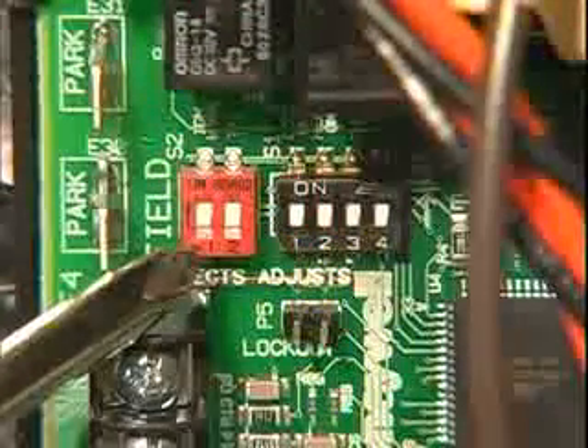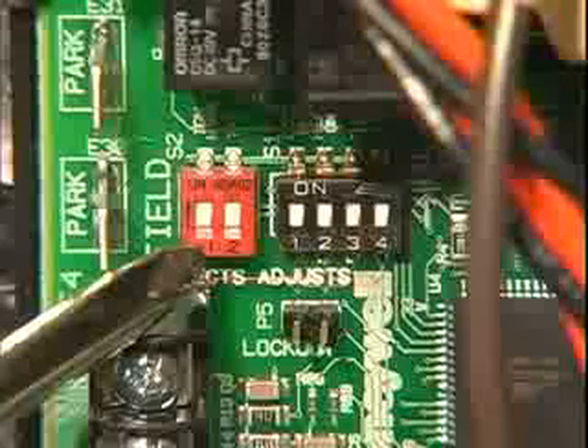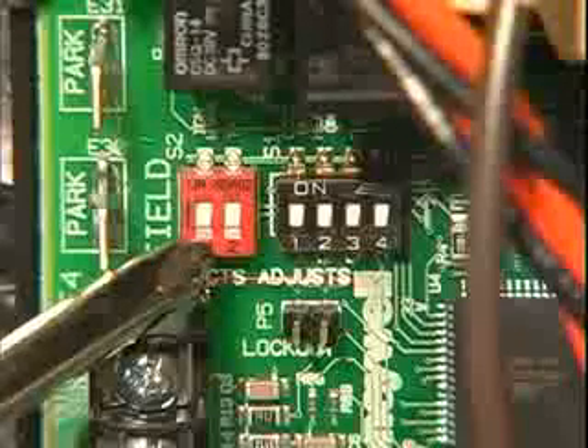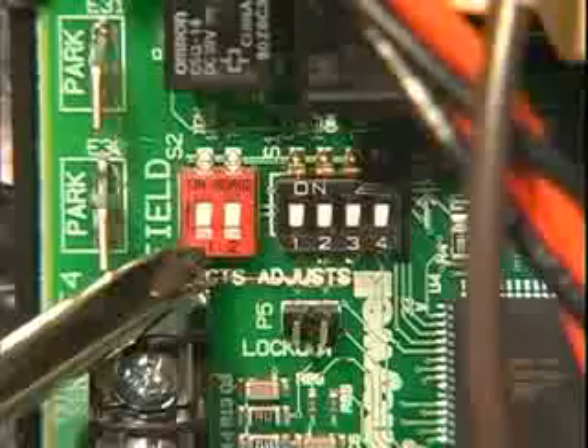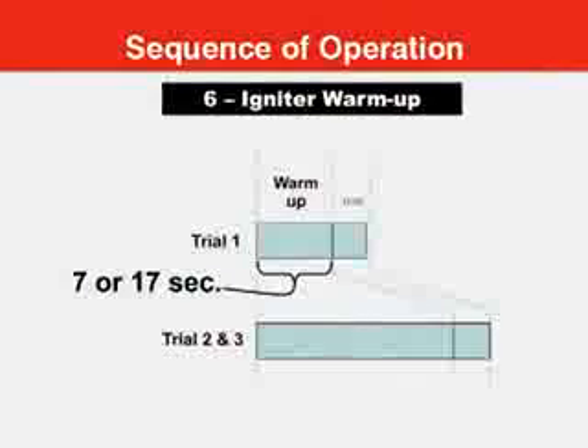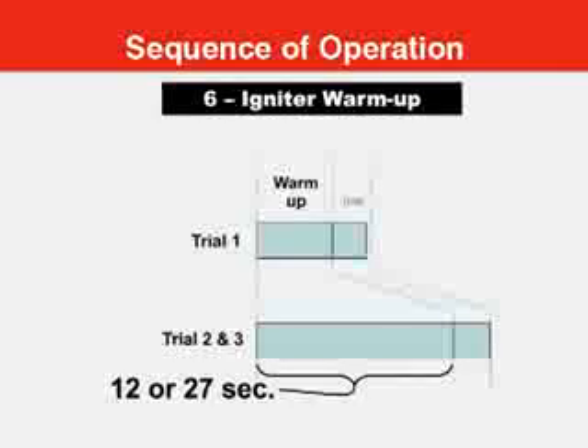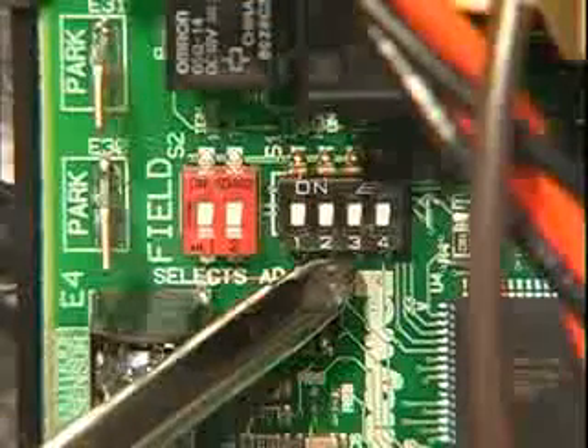That completes the wiring. The next step is to set the dip switches to get the right timings for our furnace. These 2 switches set the safety timings: igniter warm-up time and trial for ignition time. Igniter warm-up can be either 7 or 17 seconds for the first trial, with 12 or 27 seconds on trials 2 and 3. Trial for ignition can be either 4 or 8 seconds. Get these timings off the old control. The objective is to match these as close as possible without extending the safety timings of the original control. This set of 4 switches sets the fan on and off delay for heating and fan off delay for cooling.